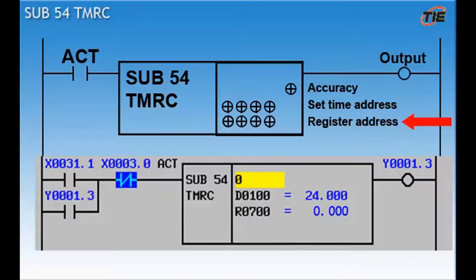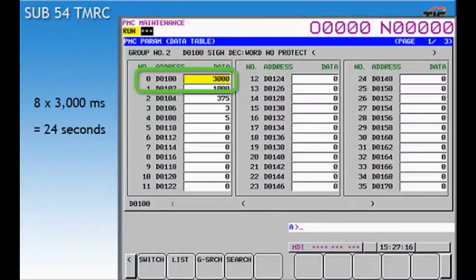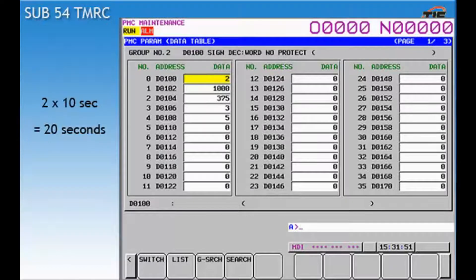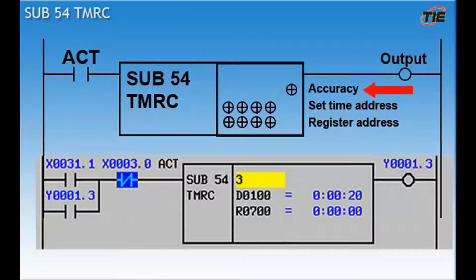The address that holds the time value is input on line 2. This is typically a data address. Note that this field will take two bytes of data. This means that if you set the starting address at D100, it will take addresses D100 and D101 to hold the timer value. This sub 54 statement is set up for an 8 millisecond accuracy. A setting of 3000 into D100 will produce a time value of 24 seconds. 8 times 3000 milliseconds equals 24 seconds. If I change the accuracy setting to a 3, this will give me an increment of 10 seconds. By setting D100 to a 2, I will end up with a 20 second timer. Timer ranges can be set from 8 milliseconds up to approximately 546 hours. That's a lot of time.